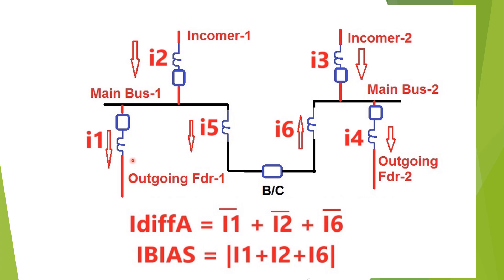The differential current has been shown for the bus bar relay for the two main bus system. The current for incomer one and incomer two is i2 and i3, and outgoing feeder one and outgoing feeder two is i1 and i4. Since i4 is greater than i3, the remaining current flows from main bus one towards main bus two, with i5 equal to i6 equal to i4 minus i3. The differential current for zone A, i_diff_A, is the vector sum of i1 (outgoing feeder one), i2 (incomer one), and i6 (CT on the main bus two side). The bias current is the scalar sum i1 + i2 + i6.